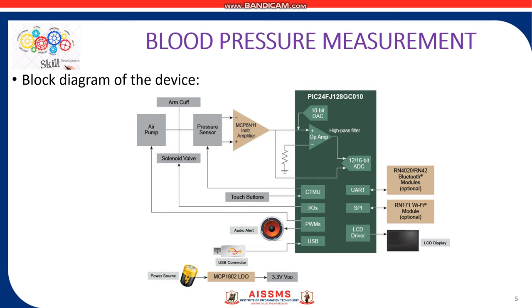The signal from the pressure sensor is conditioned with an instrumentation amplifier before data conversion by an ADC. The systolic pressure, diastolic pressure, and pulse rate are then calculated in the digital domain using an algorithm appropriate for the type of monitor and sensor utilized. The resulting systolic, diastolic, and pulse rate measurements are displayed on the LCD.